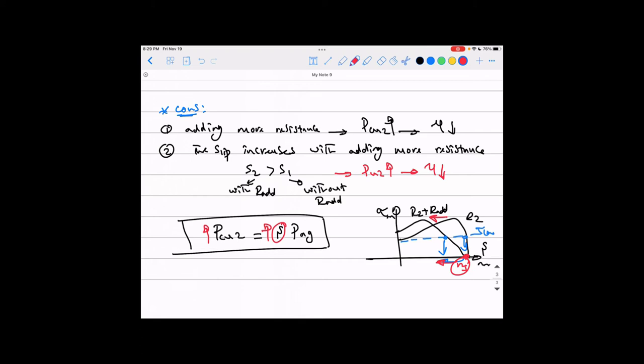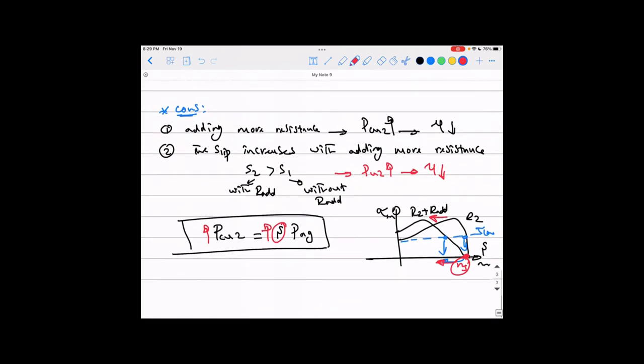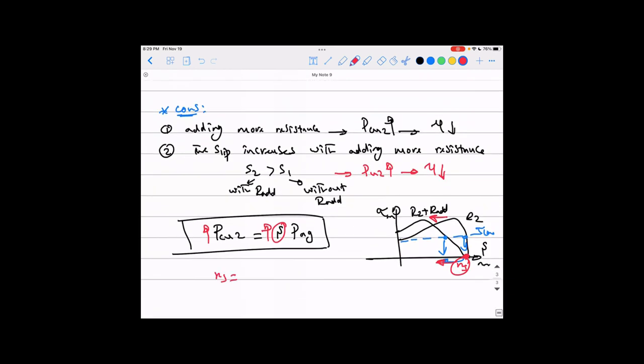With any reduction in speed while the synchronous speed remains constant, the slip will increase, and we don't like this because an increase in slip increases rotor copper losses and reduces the machine's efficiency. So: increasing rotor resistance increases stability range (a pro), but it also increases slip and copper losses (a con).